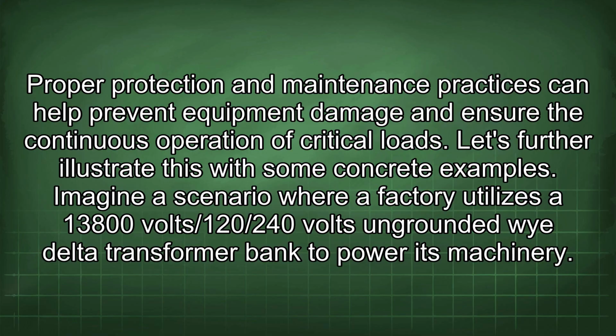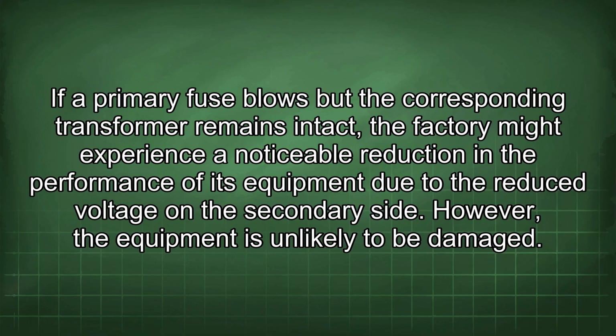Imagine a scenario where a factory utilizes a 13,800 volts/120/240 volts ungrounded Wye delta transformer bank to power its machinery. If a primary fuse blows but the corresponding transformer remains intact, the factory might experience a noticeable reduction in the performance of its equipment due to the reduced voltage on the secondary side. However, the equipment is unlikely to be damaged.